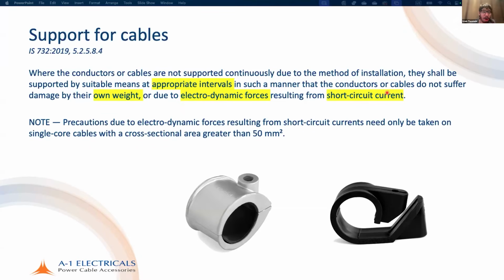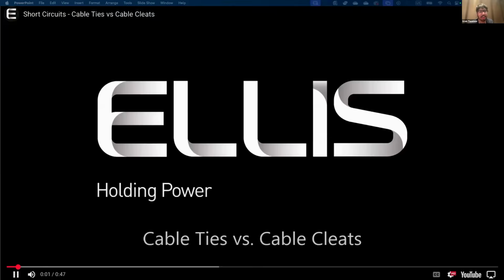Now, this is very, very, very important. One thing is supporting the cables, and making sure they don't collapse under their own weight. But the electrodynamic forces are a particular concern. I'll show you a video. When you have single core cables, particularly greater than 50 square mm, and a short circuit occurs, even for 0.1 second, which is enough time for a fuse to activate, there is a massive effect, an electrodynamic force that rips through these cables, and it can cause serious damage, and it can even badly injure or kill somebody. Here is a video that shows you what happens when no cleats are used or a cable tie is used and where cleats are used. It's just a generic video we've pulled out.